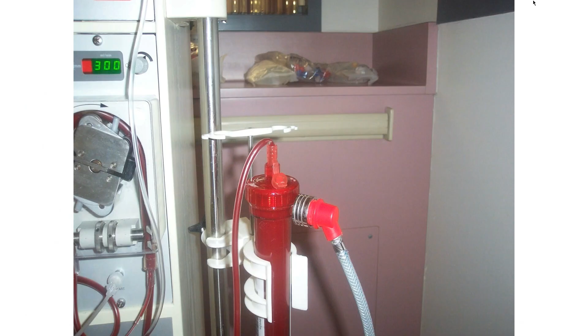Okay. This obviously is a kink in the tubing, and that can cause hemolysis. Is it being monitored by any of the systems in our machines? No, it's not, because it's post-dialyzer. I mean, it's pre-dialyzer. That's the arterial. So what would happen is your TMP is going to possibly have a negative pressure rise, right? And so that would be the indication. But it may not, because it takes a lot of restriction to actually change the TMP. That can cause hemolysis, but it may not cause TMP changes. And that's hemolysis due to kinked tubing.